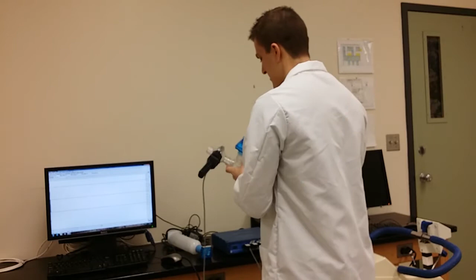Alright, so now you want to make sure everything is calibrated. First we're going to do the airflow calibration. So you're going to click on the right side over here on the scale bar, left click it, and you're going to see this little box come up. You're going to first click the scaling button, and while you're doing all this, make sure your spirometer is steady and upright. So you click scaling, you enter 0 for the Cal1 scale value, and then you want to look at your Cal1 input value and subtract 3,000 from that and put it in Cal2, which has already been done here. And then you want to change the Cal2 scale value to 10, which has already been done, and then click OK when you're done that, and click OK again.